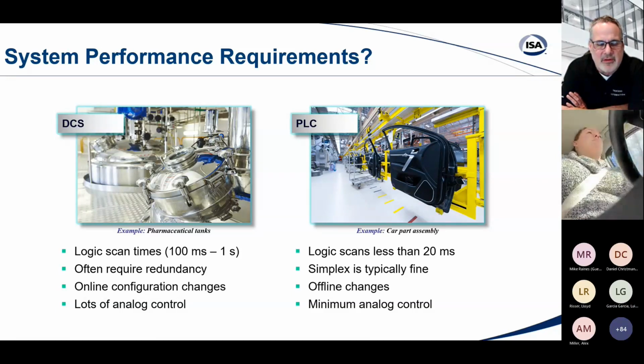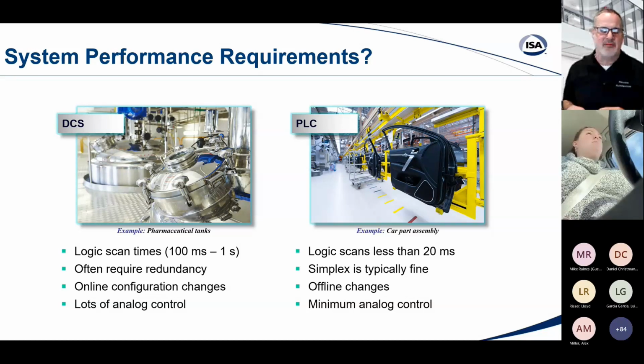And again, as I mentioned before, it's really based on having the advantage of dealing with lots and lots more analog control. Whereas on the PLC side, simplex is typically fine. Online changes aren't really a necessity, and they can do analog control, of course, but they don't have a huge amount of typical operation for analog control.